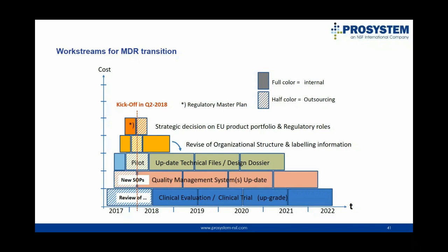We recommend to kick off some pilots to figure out how the proper documentation on labeling information and other details can be organized. And after your quality system has been adapted to ISO 13485:2016 plus MDR requirements, and you have clearly defined SOPs on what the content of a technical documentation is, then you should run on a quarterly basis to upgrade existing tech files from MDD to MDR.